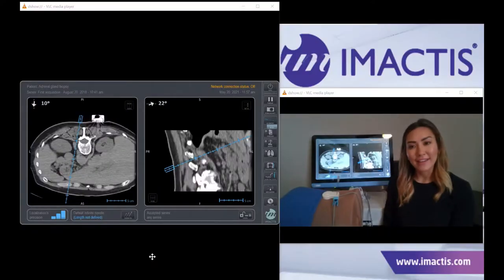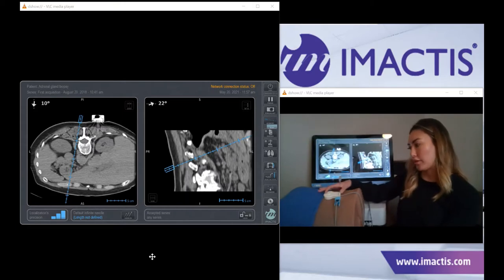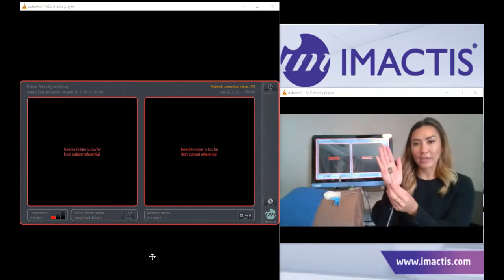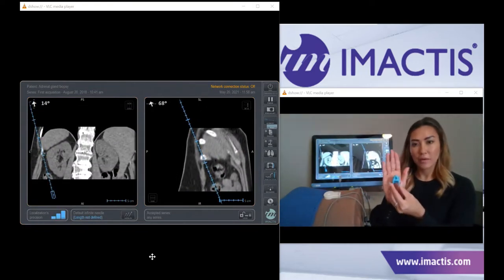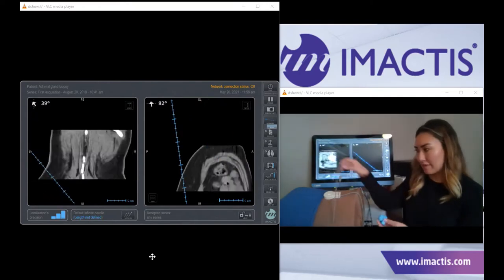My name is Sally King and I'm a clinical applications engineer with Imactis, and this is our CT navigation solution. We are an electromagnetic CT navigation system with two hardwired components: our electromagnetic emitter, which we call our fiducial, and our electromagnetic receiver, which we call our sensor. Our sensor sits inside a non-sterile needle holder with a clamp mechanism that accommodates gauges ranging from 25 to 11.